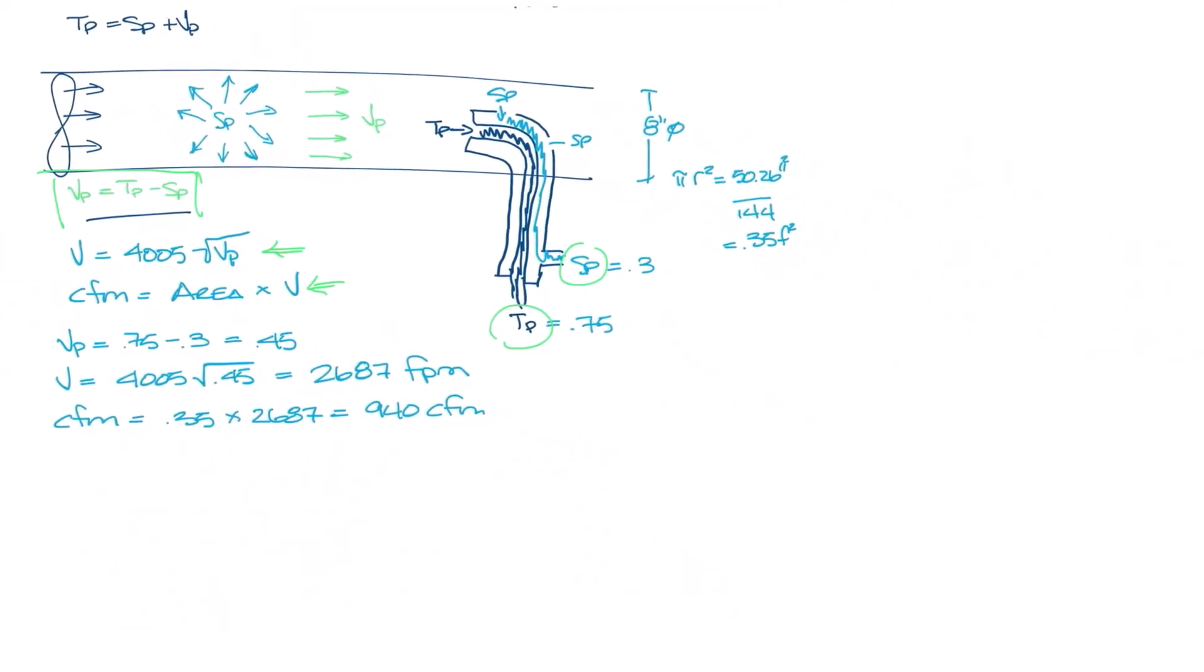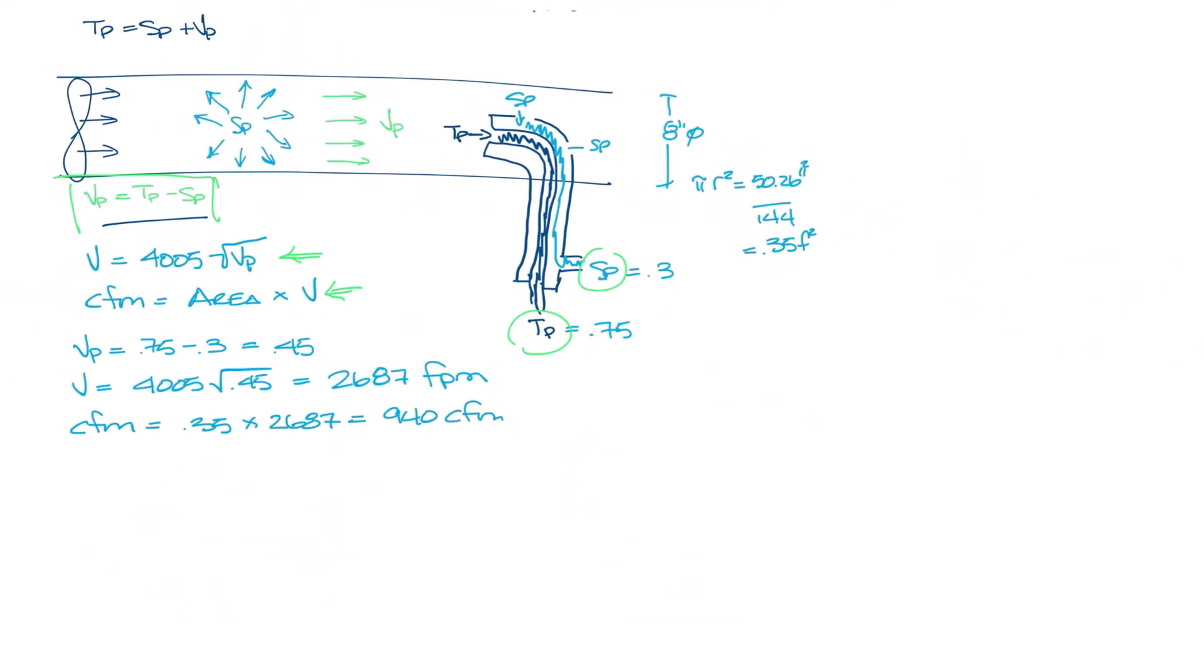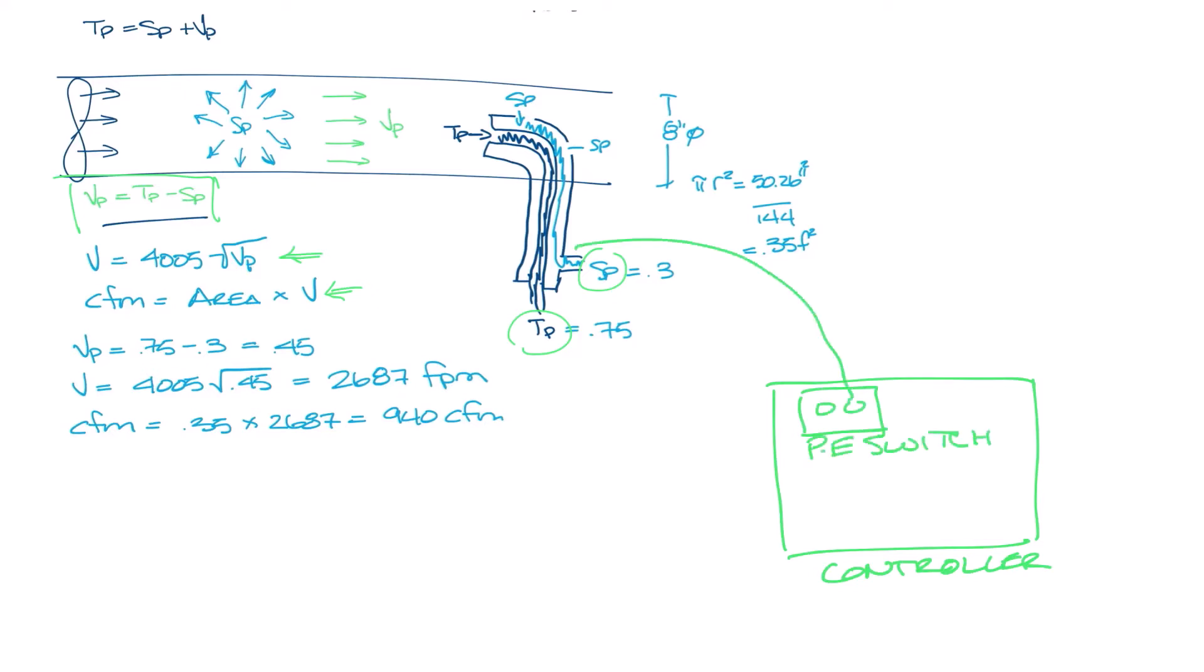Let me make a little room and draw a controller here. There are two tubes that come out of the flow sensor, one from the total pressure port and one from the static pressure port. They are connected to ports on the controller. The controller turns this pressure signal into an electric signal using a PE switch which stands for pressure to electric switch and it uses that signal to basically do this math and calculate the airflow.